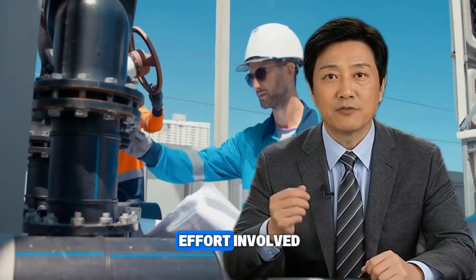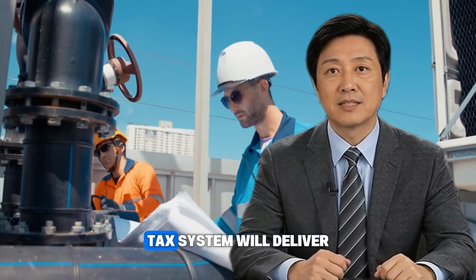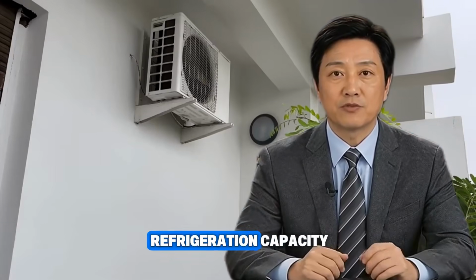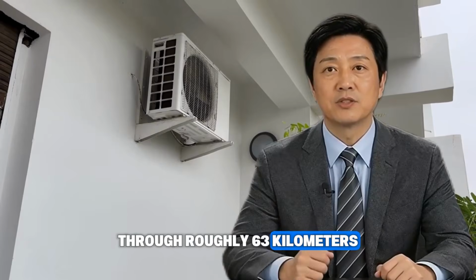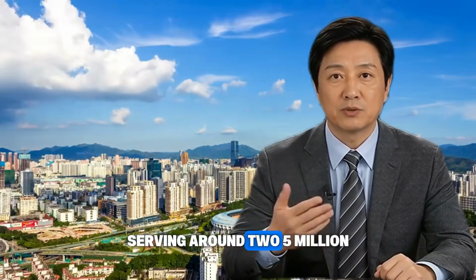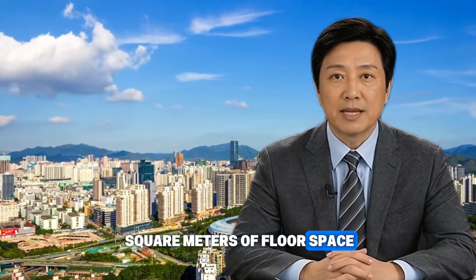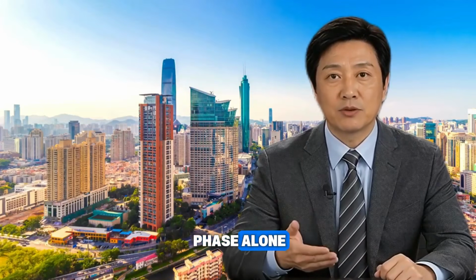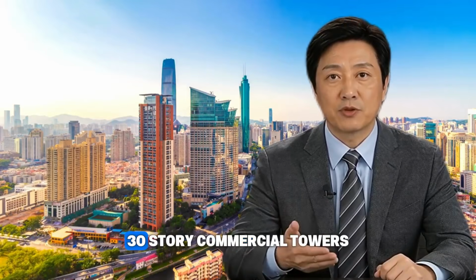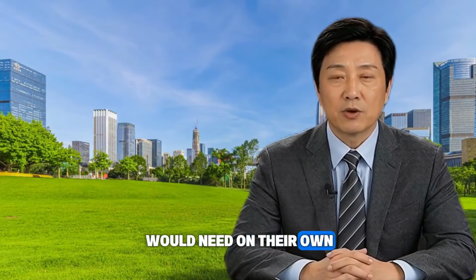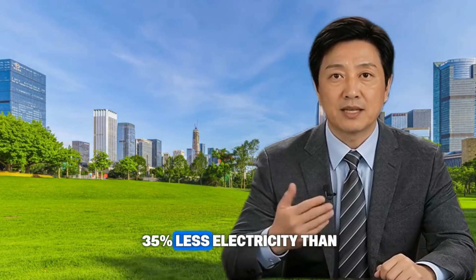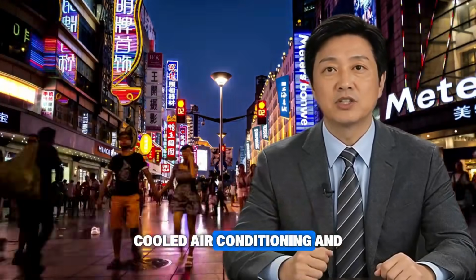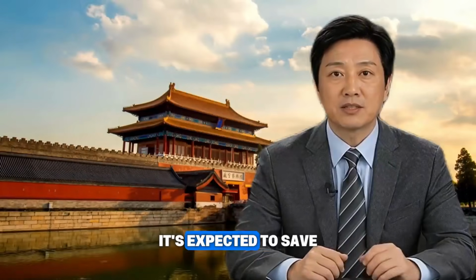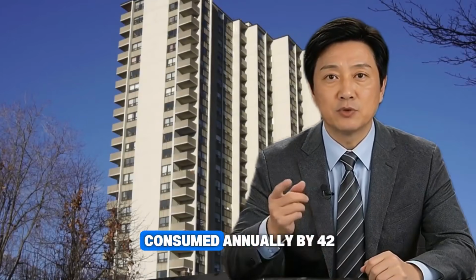The payoff matches the effort involved. Once fully completed, the Kai Tak system will deliver about 462 megawatts of refrigeration capacity through roughly 63 kilometers of seawater and chilled water piping, serving around 2.5 million square meters of floor space. Even its earlier construction phase alone provided cooling equivalent to what 40 separate 30-story commercial towers would need on their own. The system consumes about 35% less electricity than conventional air-cooled air conditioning, and once it's fully operational, it's expected to save around 138 million kilowatt-hours of electricity every year, roughly the same amount consumed annually by 42,000 households.